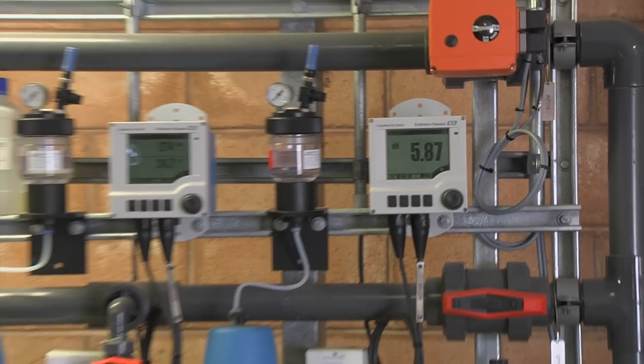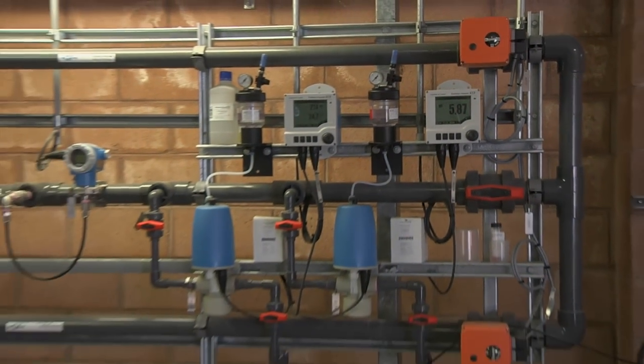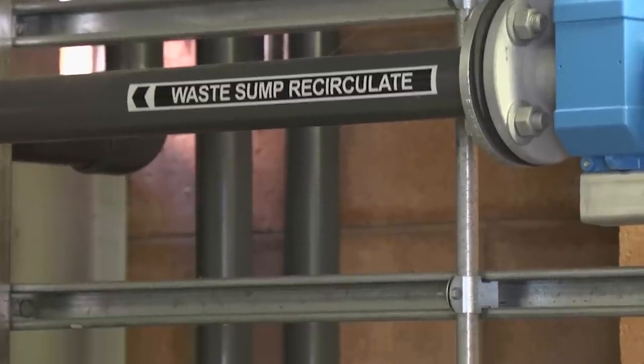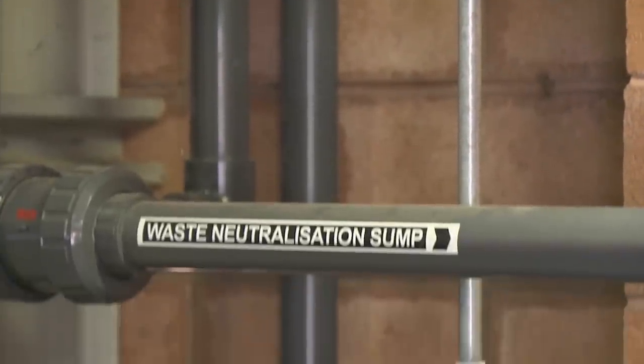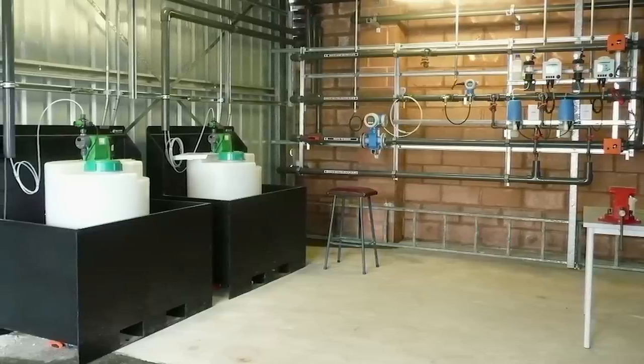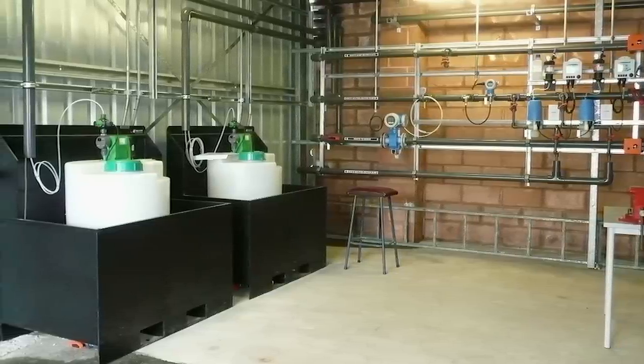We also have space for containerized plants. Wastewater from chemical cleaning of desalination systems is neutralized before discharge to the sewage system. Permeate and concentrate are combined and flow to a recharge bore as part of the centre's managed aquifer recharge system. This allows continuous operation of units being tested.